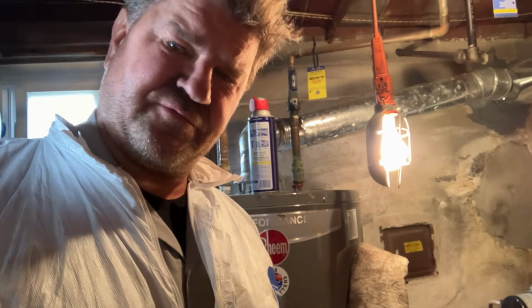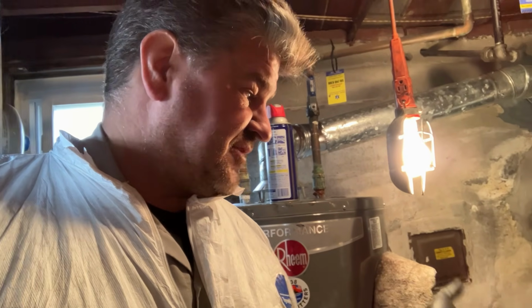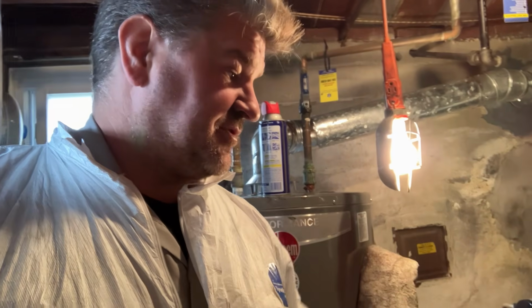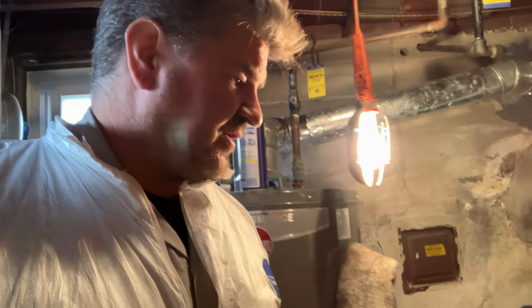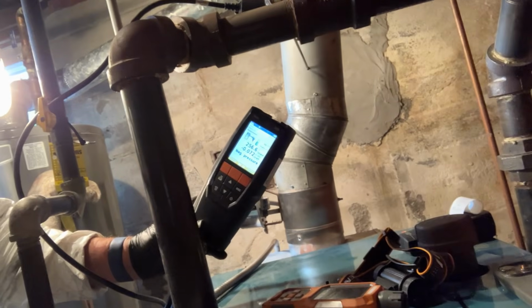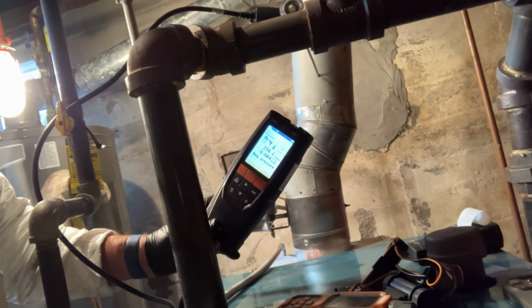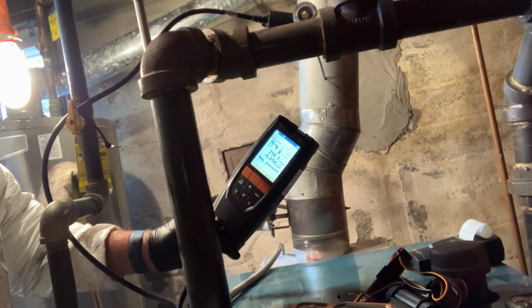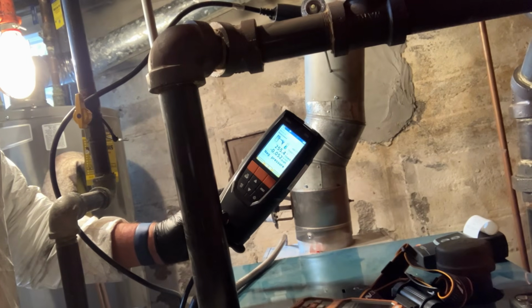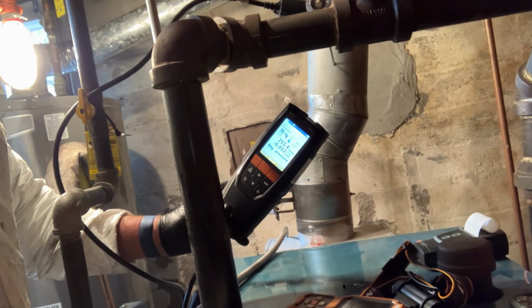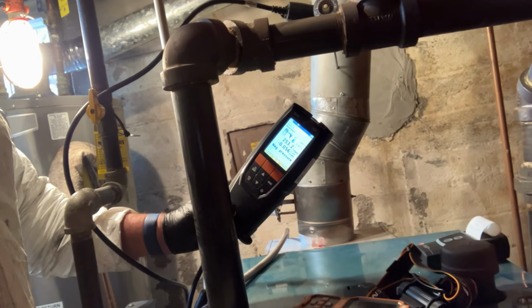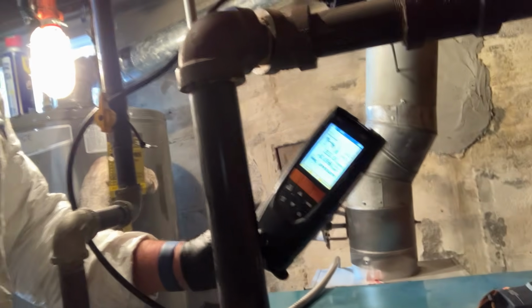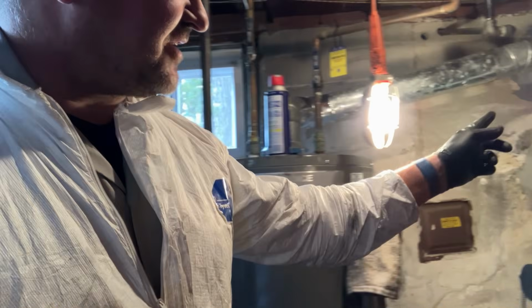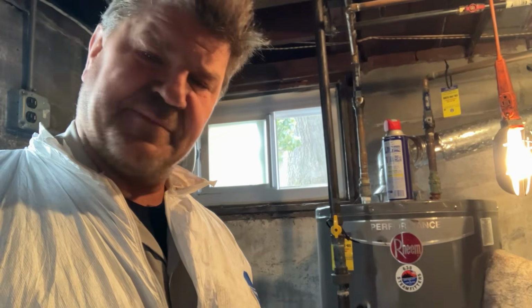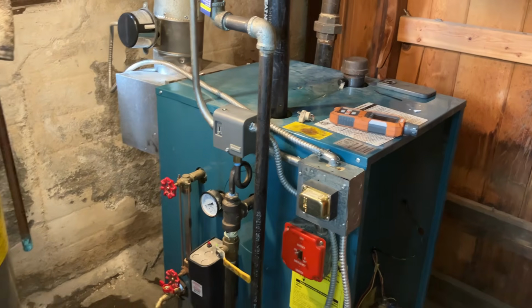Because you'll know if you have exhaust gases spilling out of that, or your stack, your flue is clogged. So, taking a look at our numbers, we are negative 72 thousandths, 64 thousandths, 56 thousandths, 52 thousandths, with a stack temperature significantly less, because we're diluting our exhaust gases with the available air that's here in the basement. Learn something new every day. All right, time to clean up.